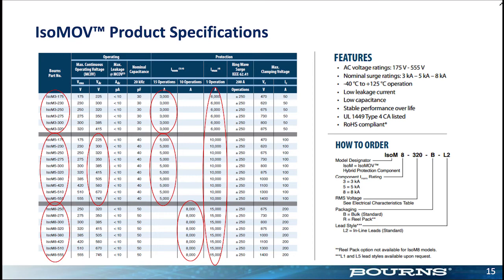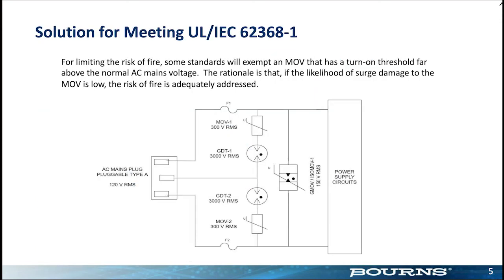So in this instance, on the IsoMOV, the typical trigger voltage or breakdown voltage is also higher than twice the clamping voltage. So the 350 volt component, for example, your typical breakdown is around 700, 750 volts or so. So that's how the test was being done.